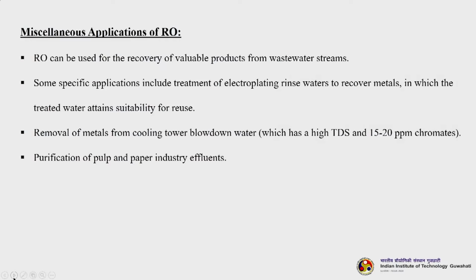There are certain miscellaneous applications of RO as well. RO can be used for recovery of valuable products from wastewater streams. Some specific applications include treatment of electroplating rinse waters to recover heavy metals, in which the treated water attains suitability for reuse, removal of metals from cooling tower blowdown water, which is at high TDS as well as 15 to 20 ppm chromates, and purification of pulp and paper industry effluents.